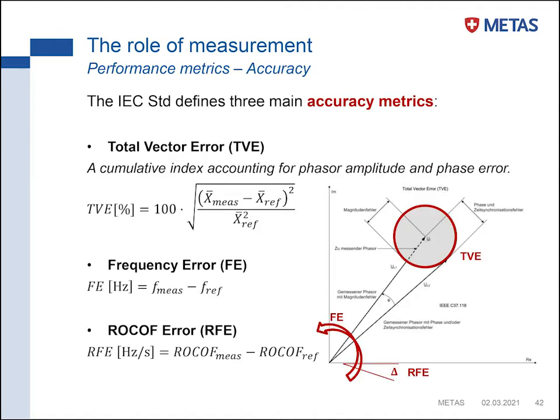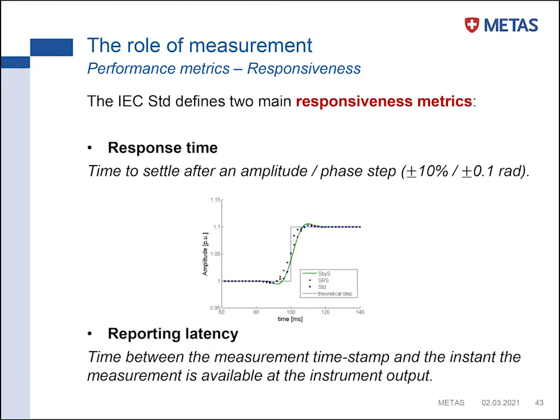What are the metrics we want to consider to guarantee the compliance with the standards? There are accuracy metrics. So there is an error on the complex quantity that is called total vector error that tells us what is the error of this complex rotating phasor in terms of amplitude and phase. There is the frequency error and obviously the ROCOF error that are quite straightforward. But we have also some metrics related to how fast is our PMU. And in particular, we consider two parameters: the response time, so the time the PMU takes to settle down after a discontinuity, an instantaneous step, or the reporting latency.